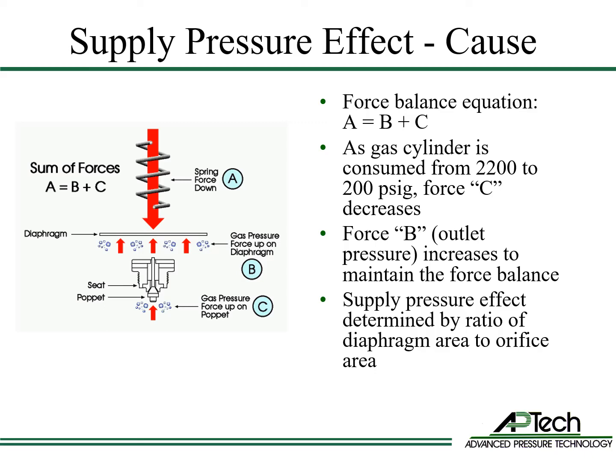In order to understand the causes of supply pressure effect, we will introduce the force balance equation. The downward force of the range adjustment spring is countered by the upward forces of the outlet gas pressure and the inlet gas pressure. As the gas cylinder is consumed from 2200 psi to 200 psi, force C decreases. For the sum of forces to be balanced, force B needs to increase as force C is decreased due to lower pressure. The supply pressure effect is determined by the ratio of diaphragm area to orifice area. Higher flow regulators generally have a lower ratio of diaphragm area to orifice area and therefore generally have higher supply pressure effect than lower flow regulators.